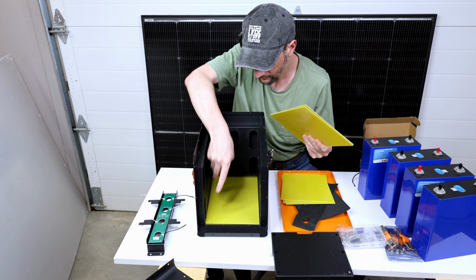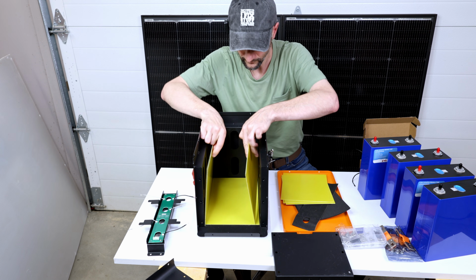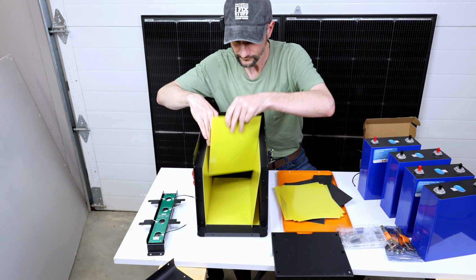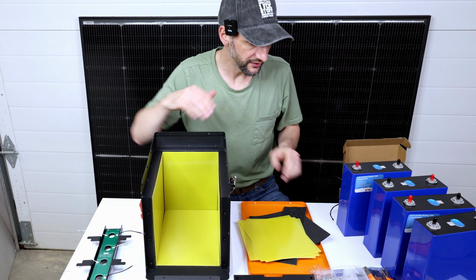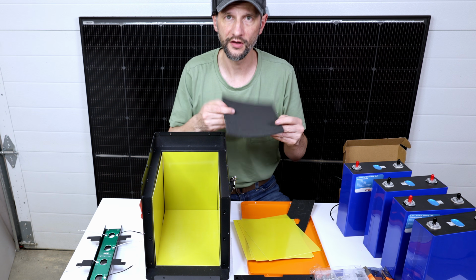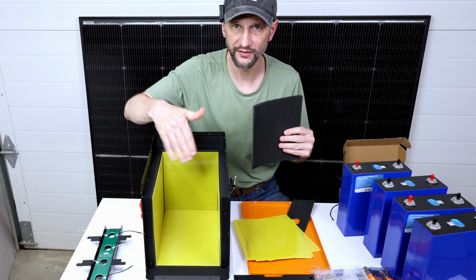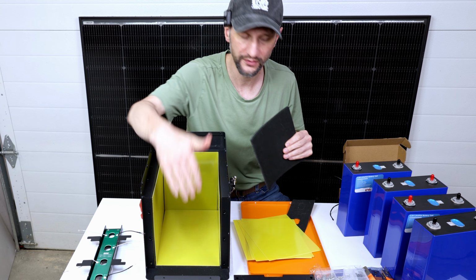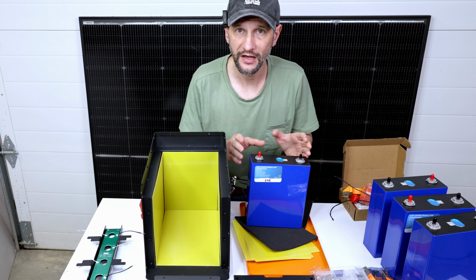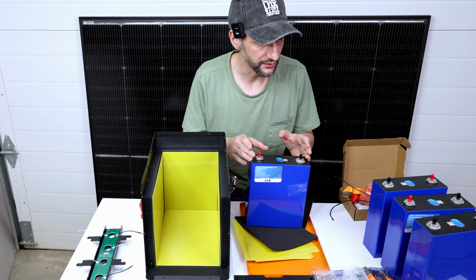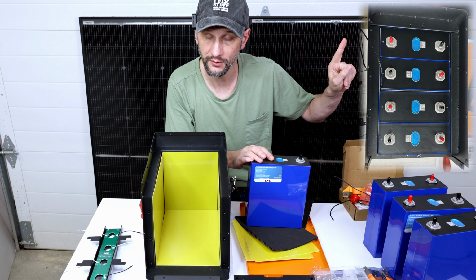First step will be to apply our phenolic insulators on the top, bottom, and sides. Now I can slide the batteries in. There are two pieces of EVA foam that will help space them out and give us a little bit of resistance against the compression plate. These batteries have to be installed in the correct orientation, so I'll show exactly what that is here on the screen for reference.